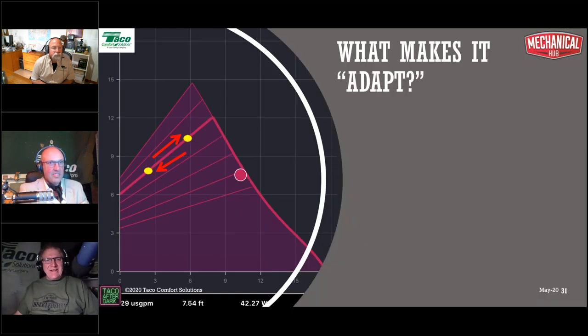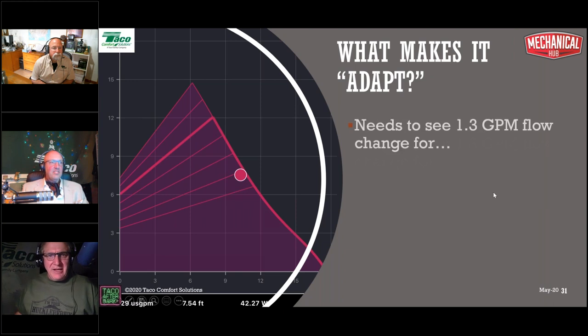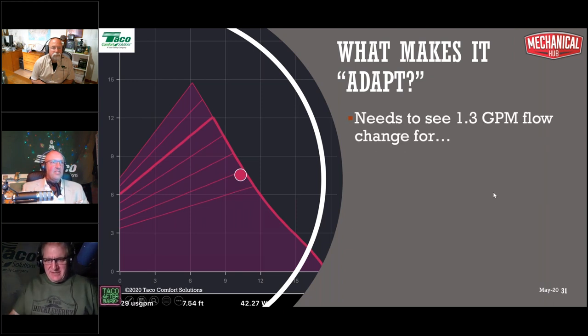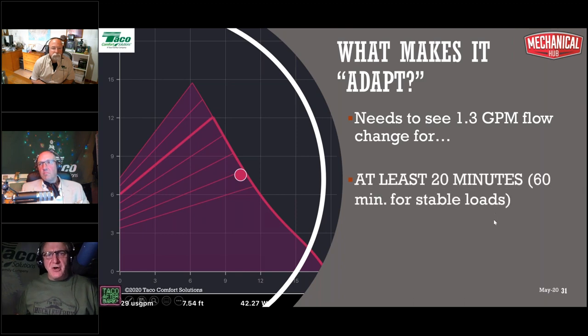All righty. What is it that makes it adapt? It needs to see changes in flow. It needs to see a change in flow for at least 20 minutes. If the load is stable, meaning we've been up and running for quite a while, it needs to see a change in flow for 60 minutes before it's going to jump from one setting to the other.